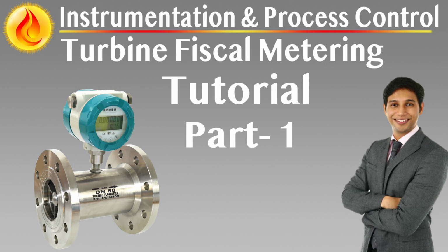Flow control and isolation mechanisms. A pneumatically actuated flow control valve regulates throughput during proving and stabilizes flow during transitions. Side-mounted declutchable hand wheels are required for manual override. Placement downstream of the turbine meter is preferred to minimize hydraulic disturbances upstream. The run terminates with dual outlet valves, one for mainline flow, one for prover diversion, both fitted with leak check provisions to ensure seal integrity prior to proving. These valves must also include position feedback and seal failure alarms.